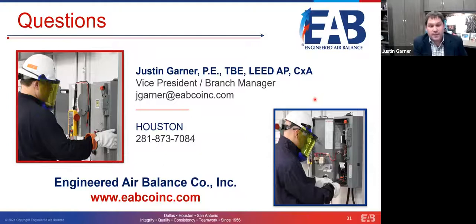Those are very good questions, and you're right, they are very similar. And this comes up in just about every class we have where we start talking about these things. So I'm glad it came up in this particular discussion. I've talked to numerous drive manufacturers, all the major ones that are out there, and they all claim that their VFD readouts are more accurate than our meters that we would use in the field. And they may very well be correct. So with that being said, you should be able to look at those displays and they should be fairly accurate.